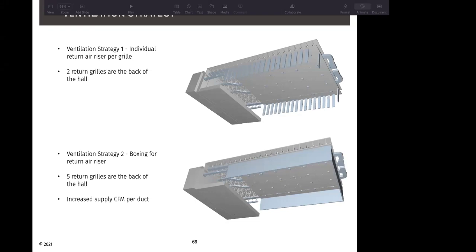The top image shows the stage side on the left and the auditorium hall in the right side, with supply air ducts coming at the false ceiling and the return riser shown at the side of the hall. In the second image, in the bottom image, ventilation strategy 2, the CFM per duct was increased, and instead of having individual return risers, a boxing was provided for the return risers, with the number of return risers at the back of the hall increased from 2 to 5.